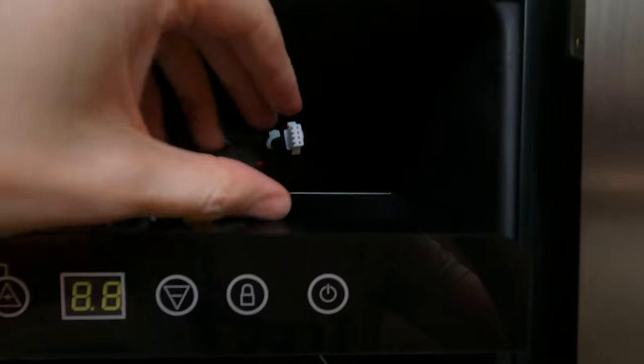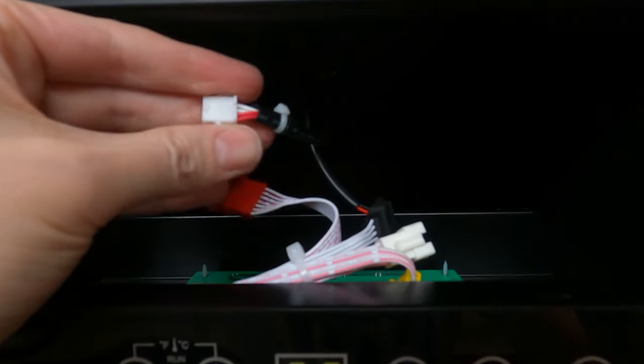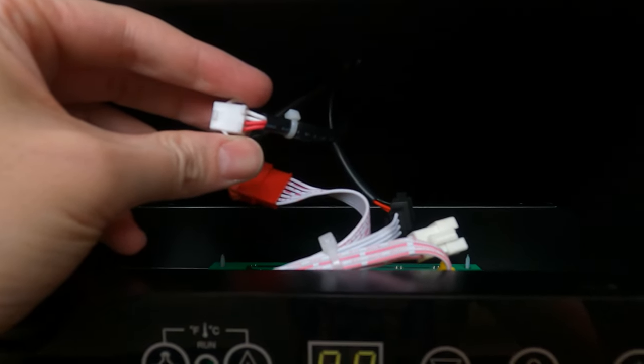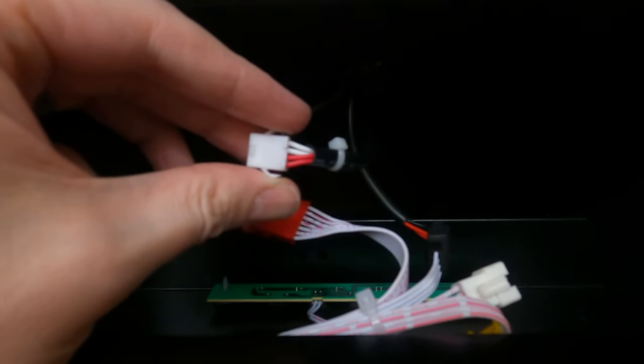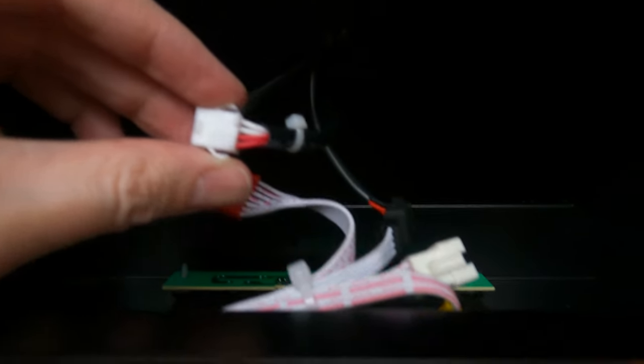Alright, so good news, bad news. The good news is there's a connector up here for both the inside temperature and then essentially the other temperature sensors, this red wire on the coils, and it's got a nice little connector here. The bad news is it's fished all the way back and around through here, which means that I'm not going to be able to fish that around. So what we're likely going to do is we're going to take this guy and we're going to cut this wire that's back here and we're going to splice on a new temperature sensor and replace it.